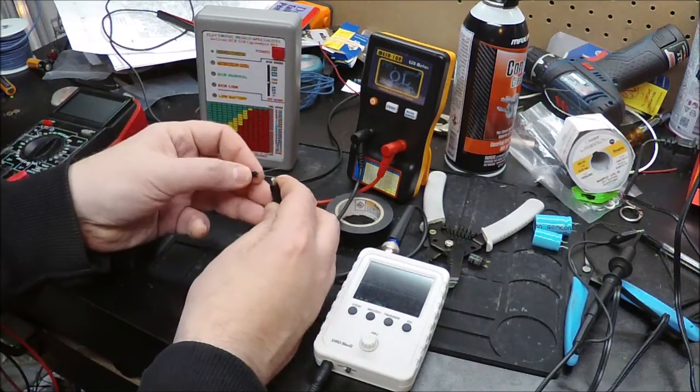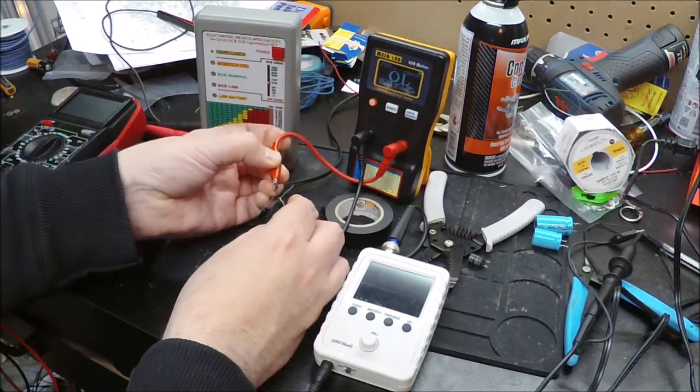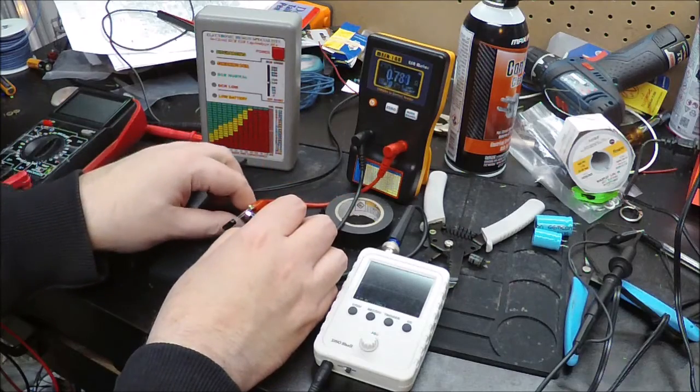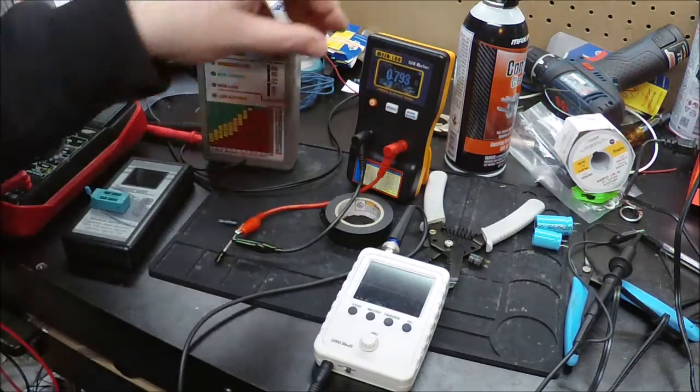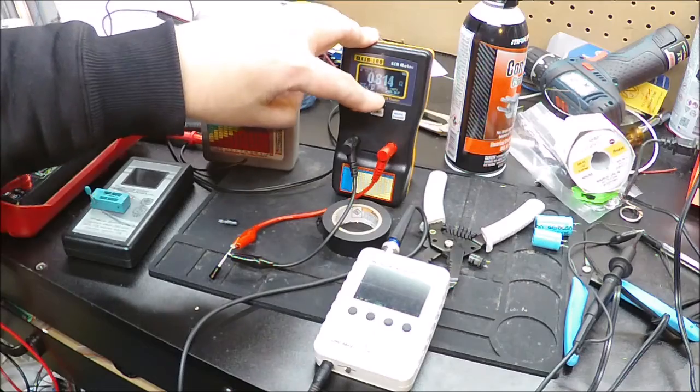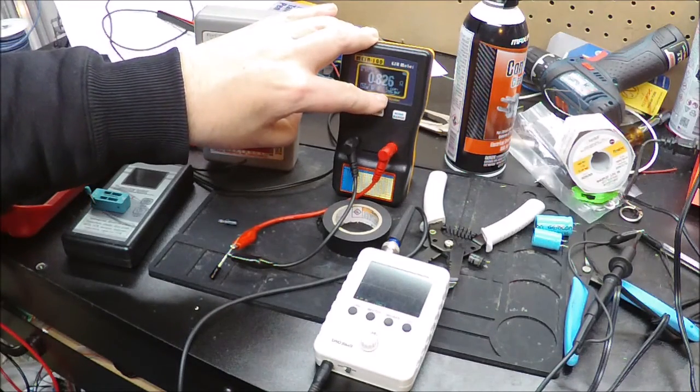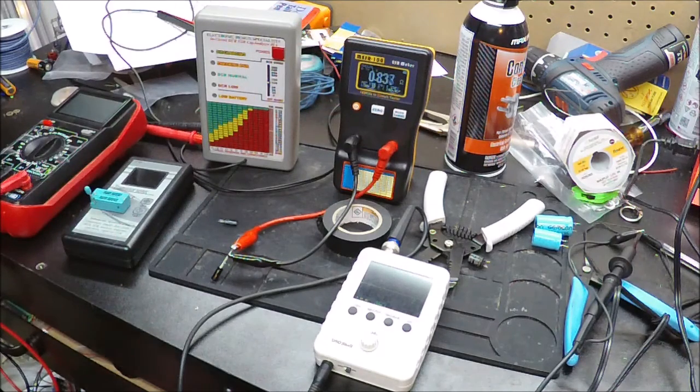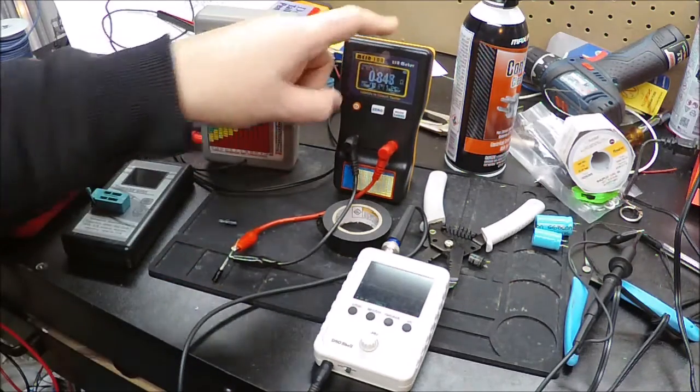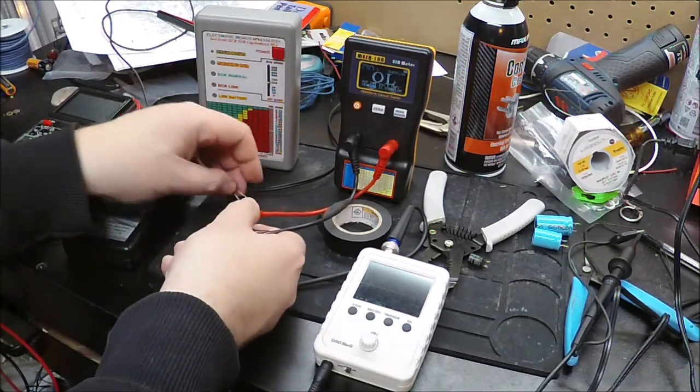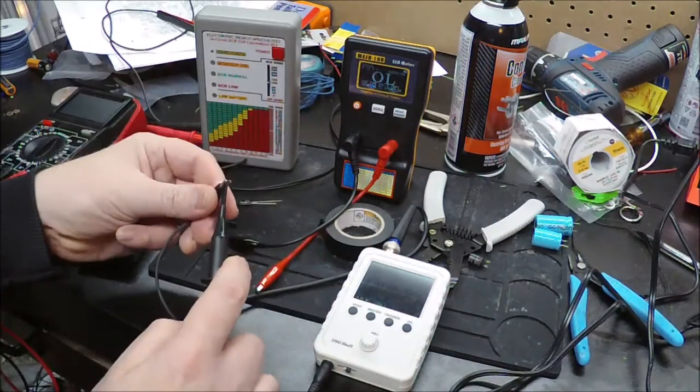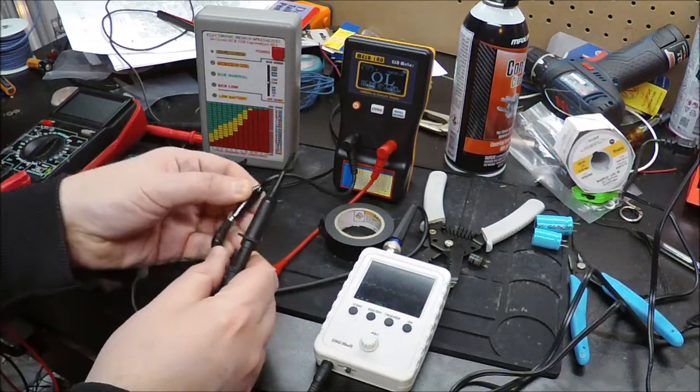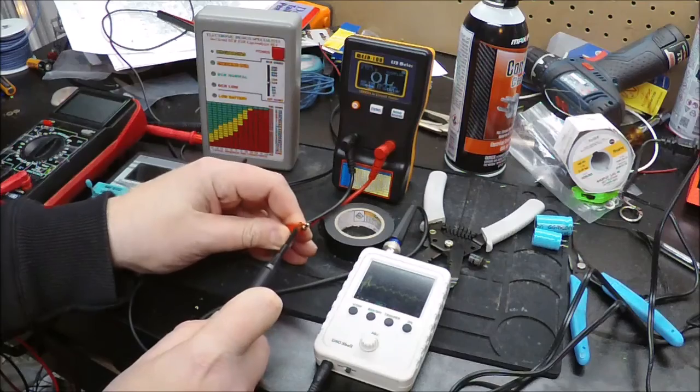Now, the ESR tester that will test our 10 microfarad capacitor here. You can see this is a brand new cap that hasn't really had any hours on it, and it is checking and showing the ESR as 0.8. And it says that if this cap is less than 200 microfarad, it would be considered acceptable, which it is, it's only a 10 microfarad. This tester is using an AC signal, I believe they said it's 100 kilohertz.